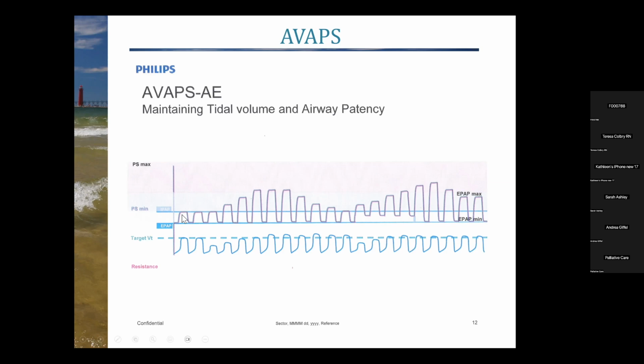This is the inspiratory, or sorry, this is going to be that expiratory range here, and then the inspiratory range. So what you see is as the patient takes a breath, it's staying within this inspiratory, expiratory range as long as it's meeting that tidal volume. It's still doing that same thing, but suddenly that tidal volume is dropping. So as the machine senses that tidal volume dropping, it's pushing up that inspiratory pressure, and expiratory is staying the same. Inspiratory is going up and it's keeping that expiratory at the baseline. It's giving more and more pressure breath by breath, and you can see the tidal volume going up. As it averages out, it's getting above the baseline there.